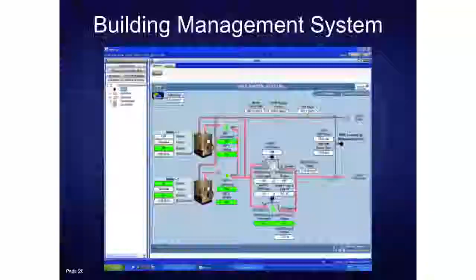So understanding that you can get down to the zone level and really meter and monitor that is incredibly powerful. Building management systems provide decent graphics now. Paying to have those graphics built out isn't cheap. But having the ability to see your duct pressures, what's going on in the building, which boilers are running, or which heat exchangers are operating and at what level, really gives you a lot of feedback on the building.